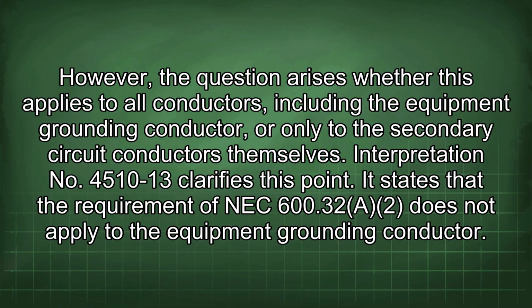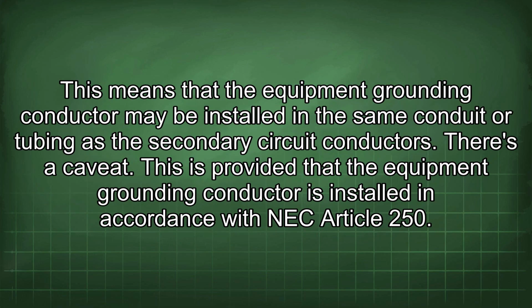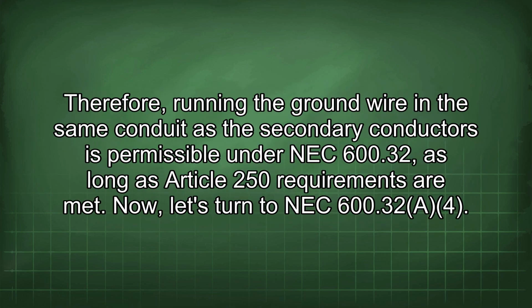Interpretation No. 4510-13 clarifies this point. It states that the requirement of NEC 600.32(A)(2) does not apply to the equipment grounding conductor. This means that the equipment grounding conductor may be installed in the same conduit or tubing as the secondary circuit conductors. There is a caveat. This is provided that the equipment grounding conductor is installed in accordance with NEC Article 250. Therefore, running the ground wire in the same conduit as the secondary conductors is permissible under NEC 600.32, as long as Article 250 requirements are met.